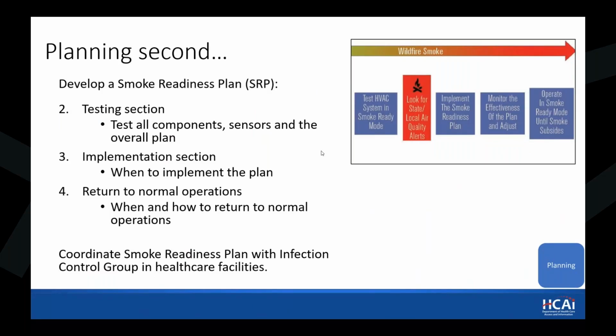The third section is that you need to be clear on when to implement it. Is it manual? Is it automatic based on the PM 2.5 level? For those of you who are HVAC engineers and use guideline 36, it now has what's called an outdoor pollution mode, which is basically inspired by wildfire smoke.